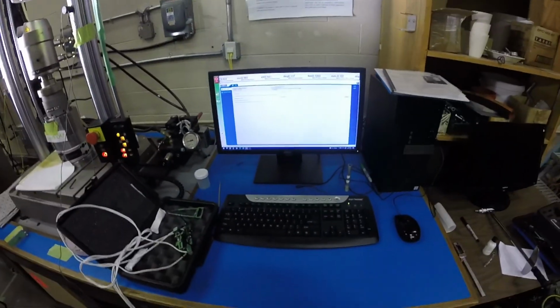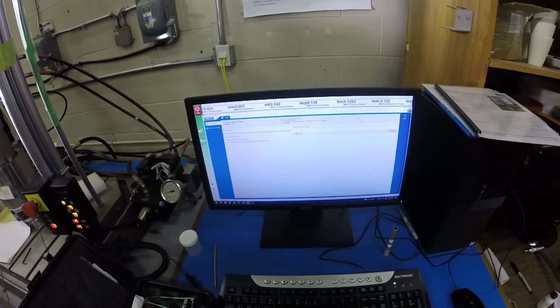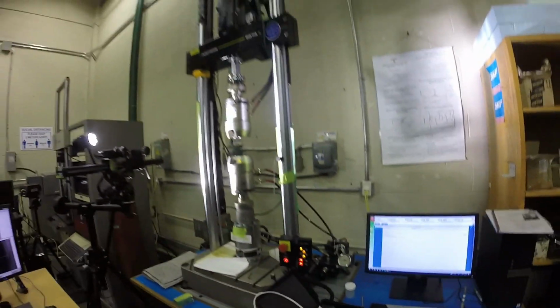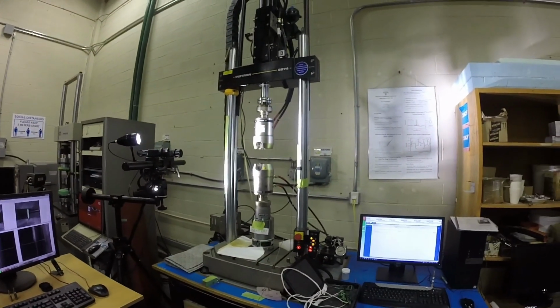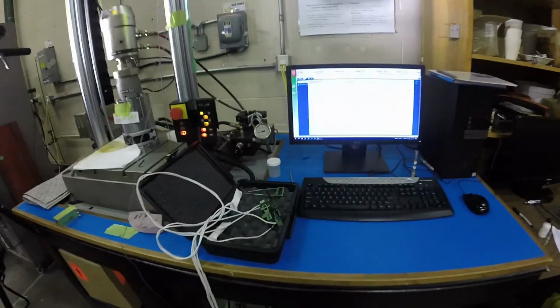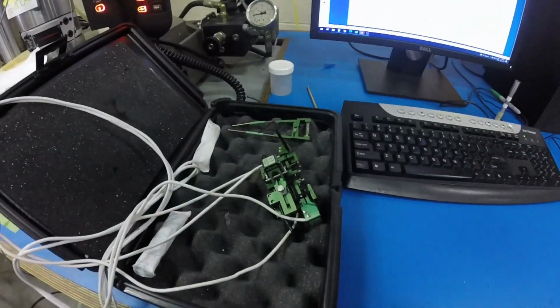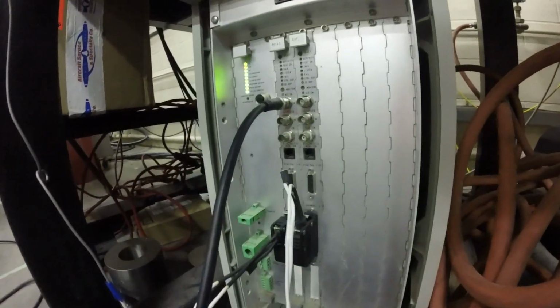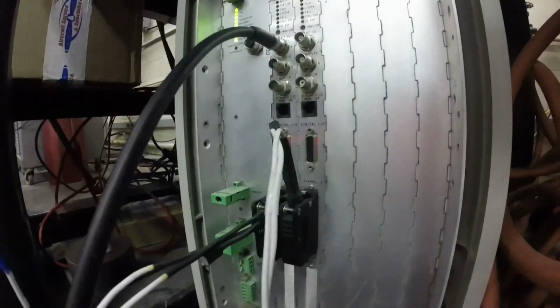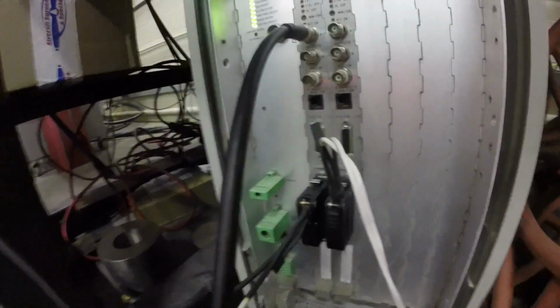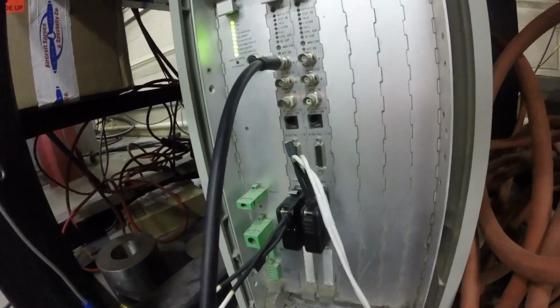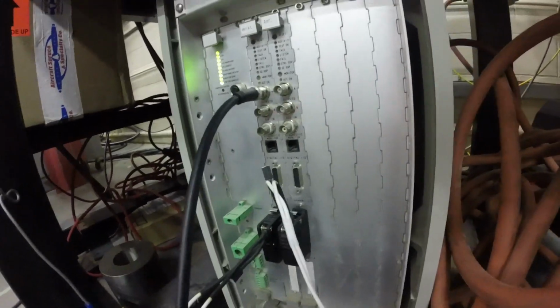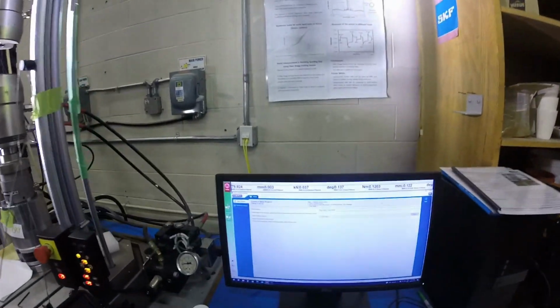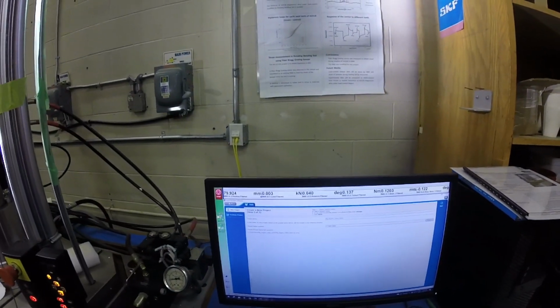So this is a video SOP, or standard operating procedure, for the Instron 8874 machine. You can see the Epsilon biaxial extensometer here connected to the two cards on channel 3, and you can see here one of them is axial and one of them is rotational. So you're going to want to make sure that those are connected and that the correct calibrations are selected for each of the two channels here and here.